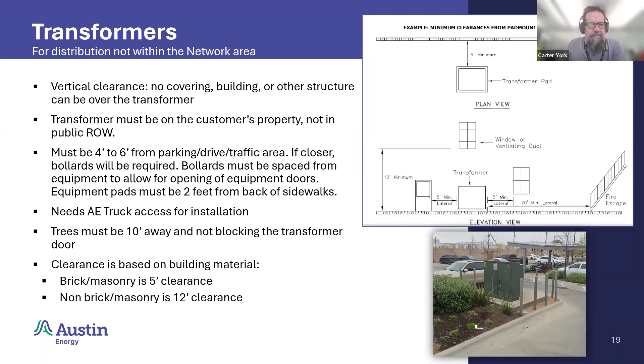The lateral clearances required for windows and doors are 5 feet minimum to the sides. Any sort of window, ventilating duct, or opening that is directly above the transformer needs a minimum of 12 feet clearance before that can begin or be present in a wall, regardless of the material constructing the wall. The landing of a fire escape, lateral clearance is a minimum of 20 feet. So in an emergency, let's say, unfortunately, something is going on with the transformer and it's on fire, or it's shorting or arcing, we need at least 20 feet before occupants of a building hit a landing from a fire escape to get out safely. Next slide, please.